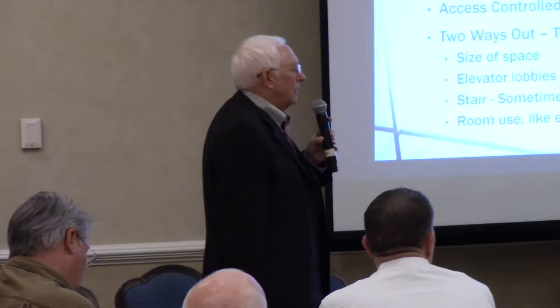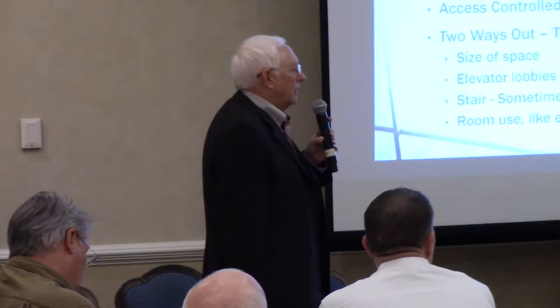A mortise lock with a deadbolt is manufactured so that on the inside handle, you turn the lever and it brings back the deadbolt simultaneously. If someone has a deadbolt on their personal office door and they've been instructed how to get out, is it okay? No — because another person might be in there. Instruction doesn't count, just as time doesn't count.